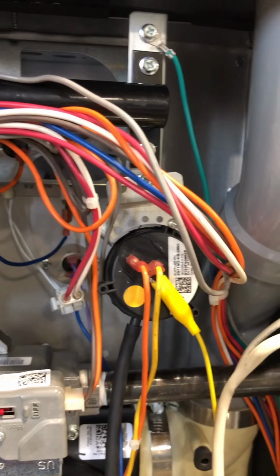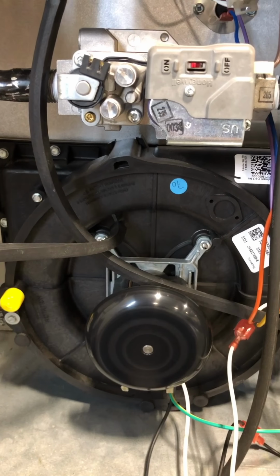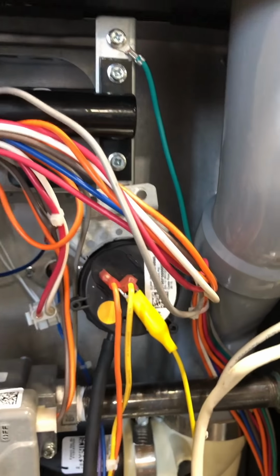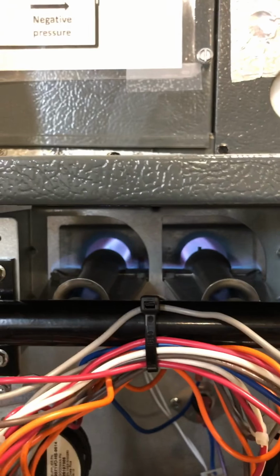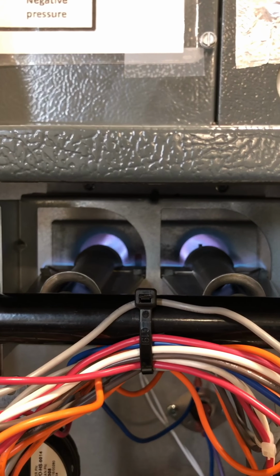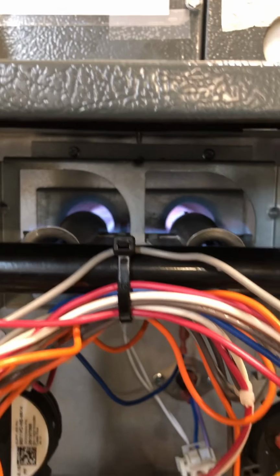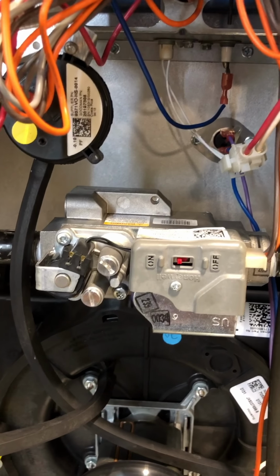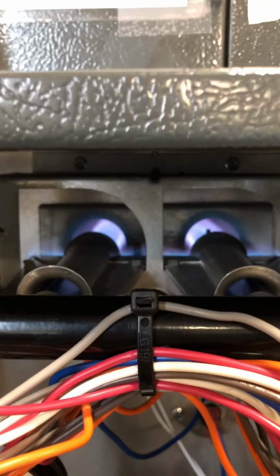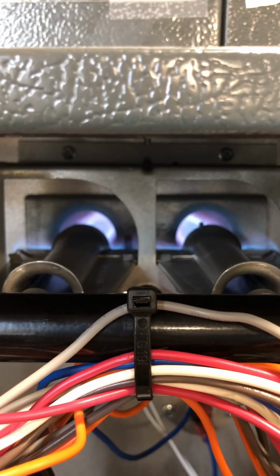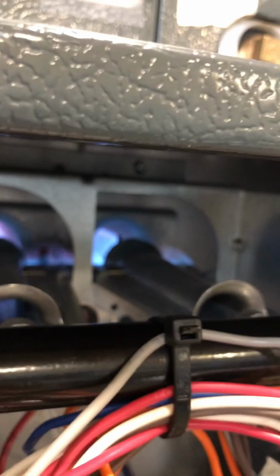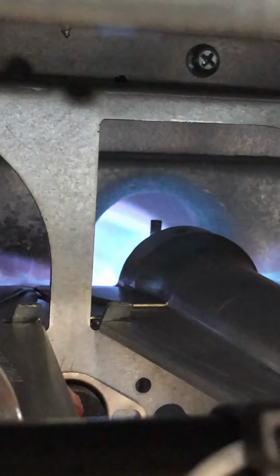So we got call for heat. Furnace board verifies that the inducer switch is open. Then it brings on the inducer. If the inducer pulls the proper vacuum, meaning all vents are clear and the inducer motor runs good, the switch will close. We will initiate hot surface ignition. It will glow red and warm up. As soon as it gets to a proper temperature, we'll energize the gas valve, which will then pump gas into our chamber. We should ignite. And then our flame sensor, which is way back there in the back, it is going to verify that our flame is burning.